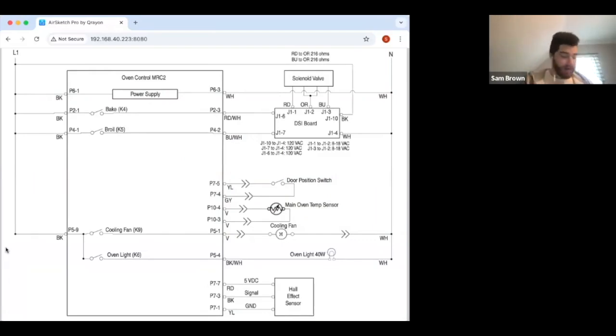What the tech actually ran into here was, we had to understand all of that to even troubleshoot this and make sure we understand what was going on. Turns out the problem was not related to that system. It was working properly, as we described. There was no interruption in the return path for ground. The board was able to sense current. What the tech did was a voltage measurement, putting a meter on the output to bake right there, and checking that with reference to neutral. And he found that at that 20 to 30 second mark into the cycle, he was losing the 120 volts here at P23.